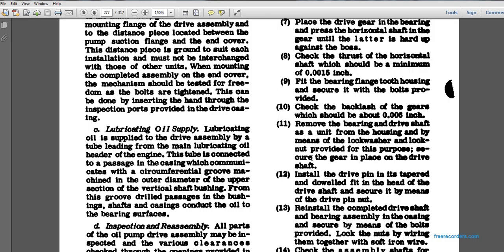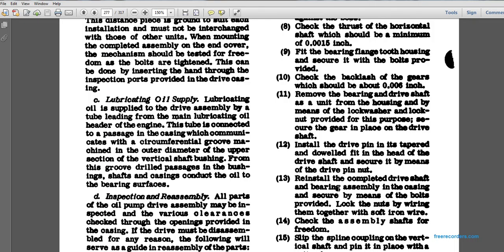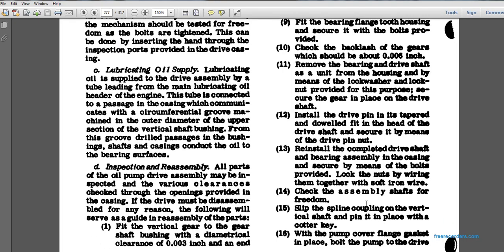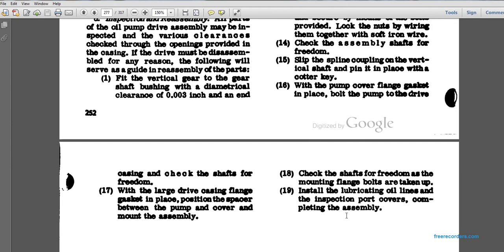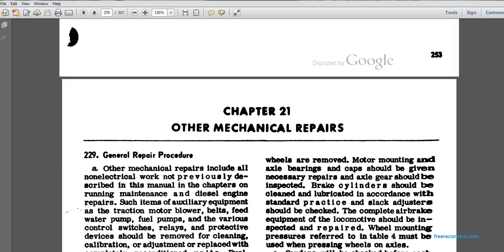Reinstall the completed drive shaft bearing assembly in the casing and secure it by means of the bolts, providing them with lock nuts and wiring them together with soft iron wire. Check the assembly of the shaft for freedom. Slip the spline coupling onto the vertical shaft and pin it into place with a cotter key. Then, with the pump cover and gasket in place, bolt the pump to the drive casing and check the shaft for freedom. Place the large drive casing flange and gasket in position with the spacer between the pump and the cover mount assembly. Check the shafts for freedom as the mounting flange bolts are tightened. Install the lubricating oil lines and inspection covers and complete the assembly. Chapter 21, Other Mechanical Repairs.